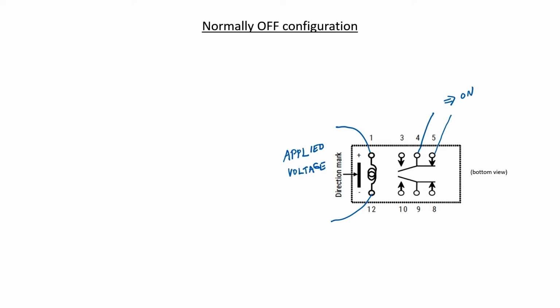Between pins 3 and 4, we have the normally on configuration. The reason why you might have a normally off configuration and a normally on configuration is because sometimes you might want the circuit to be on most of the time, and then you can apply a control voltage in order to switch something off temporarily. The normally off configuration, however, would be off all the time unless you apply a voltage across the coil.